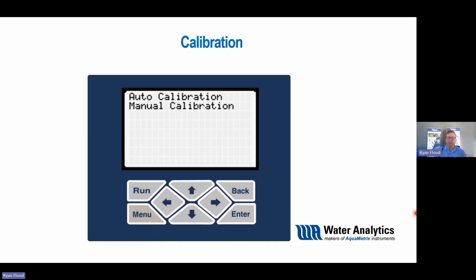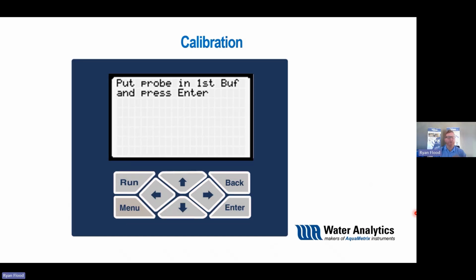The auto calibration is a really nice feature of our 2250 series, and it helps detect what reference solution you're putting the sensor in. And this can be really good because if it can't detect it, it can indicate that your sensor may need more than just calibration, right? It may need that new salt bridge, may need a little bit of cleaning. And that's an early indication that you may want to do things a little bit differently. And you don't have to then waste your time with performing the calibration. You can relook at the sensor first and see, is it in good health? So there's your first indication of, is your sensor in good health?